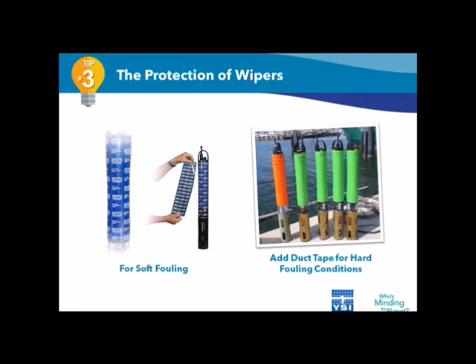These would be items like shrinkable plastic sleeves, which form a protective layer between your instrument and the environment and make cleanup much easier. These typically work well in soft fouling environments where things like small aquatic worms, mud, and some algae would otherwise coat your sonde from top to bottom. For hard biofouling, these sleeves need a layer of copper tape or duct tape over them, because barnacles can penetrate the plastic.